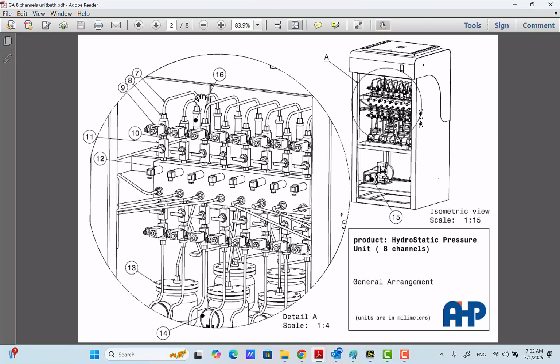Yes, the other point is the one-way valves. In each station, you also have a one-way valve in the backside. When you look inside the pressure unit, you will see a one-way valve, that is a check valve, for each line.